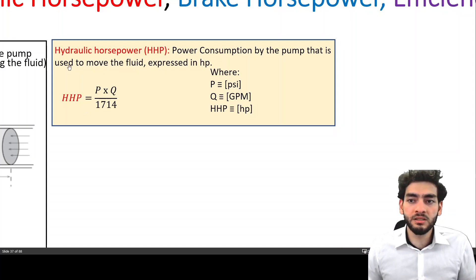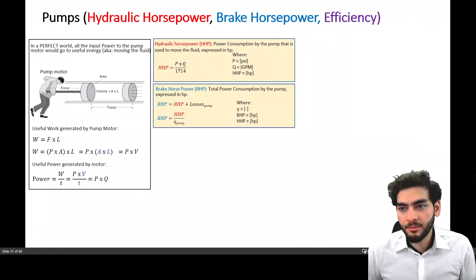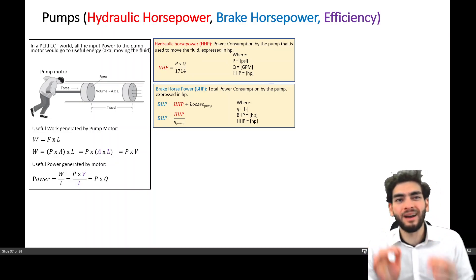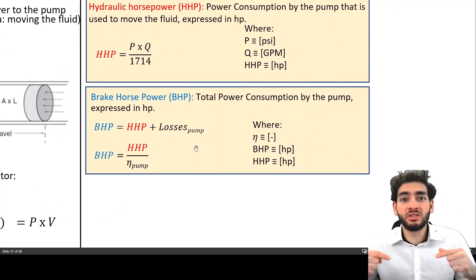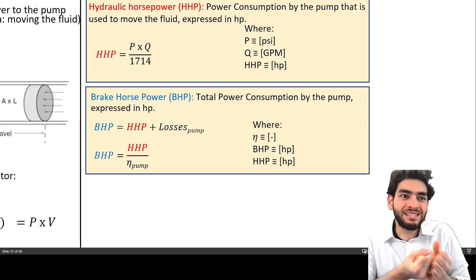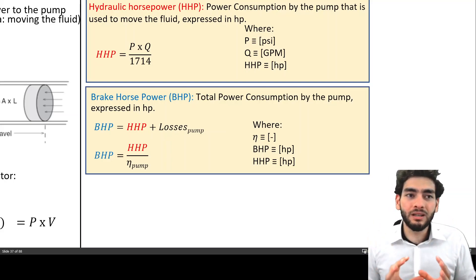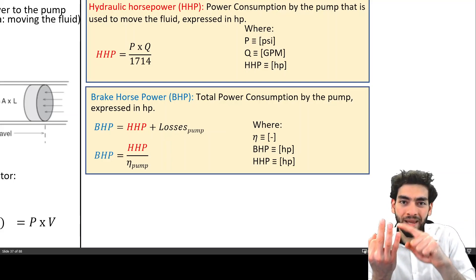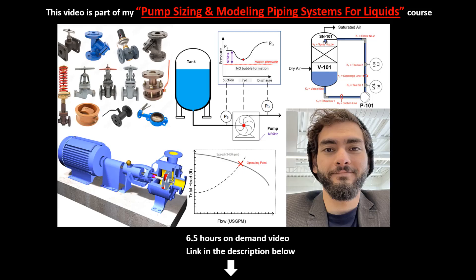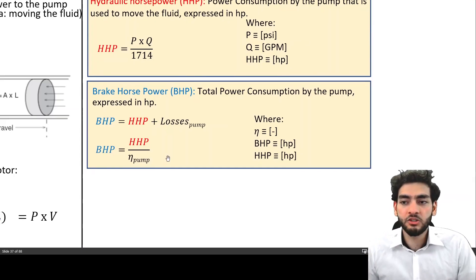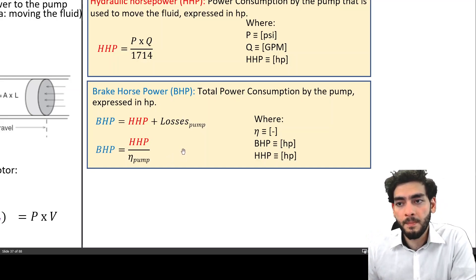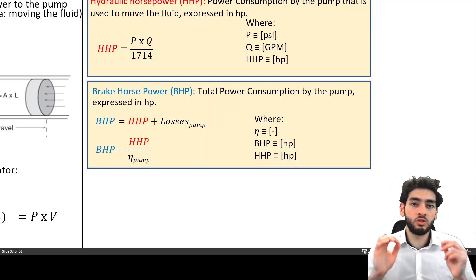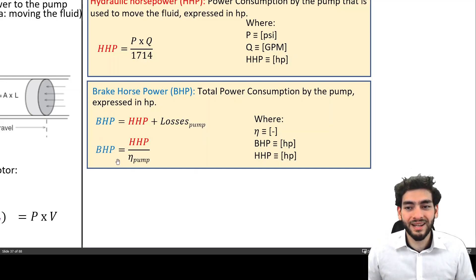The second parameter is brake horsepower, which is the total power consumption by the pump. It includes the hydraulic horsepower — the useful energy absorbed by the fluid — plus the pump losses from the previous slide: mechanical losses, volumetric losses, and hydraulic losses. Brake horsepower can be calculated in two ways: by adding hydraulic horsepower to the pump losses, or, if the pump supplier provides a pump efficiency, using that efficiency equation.